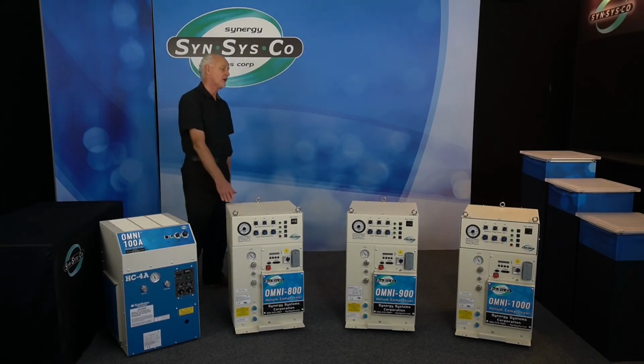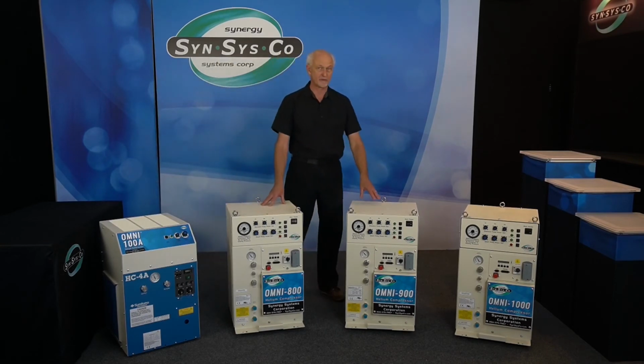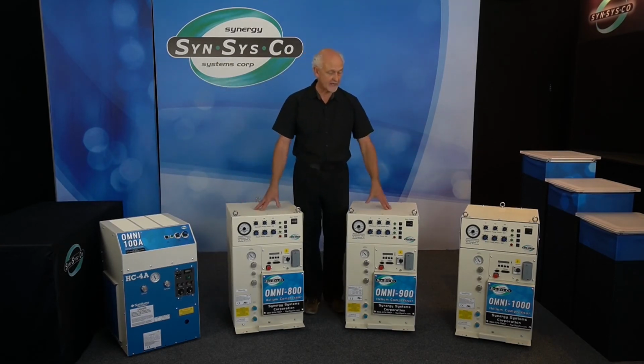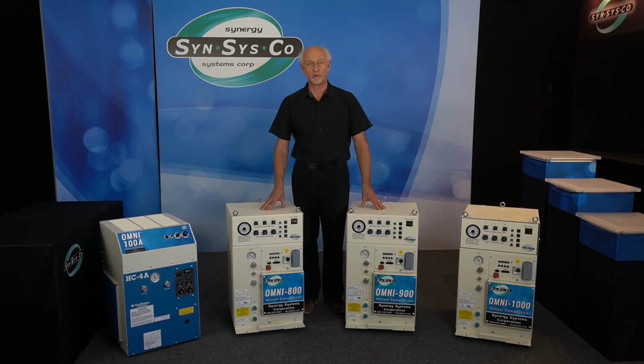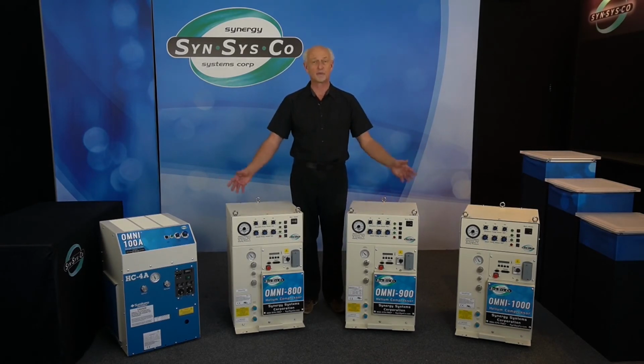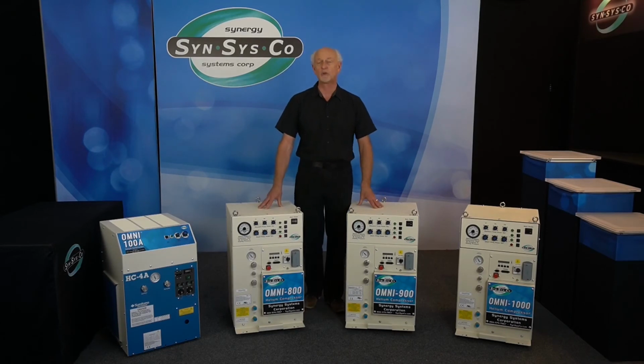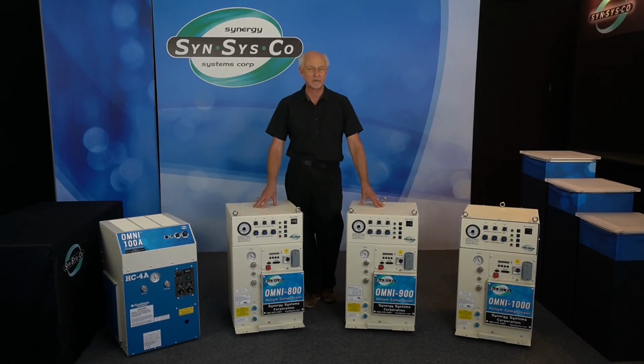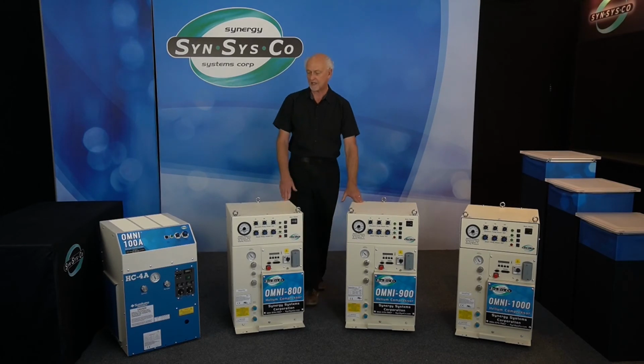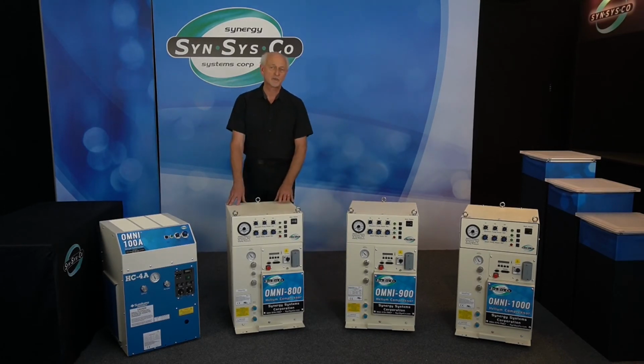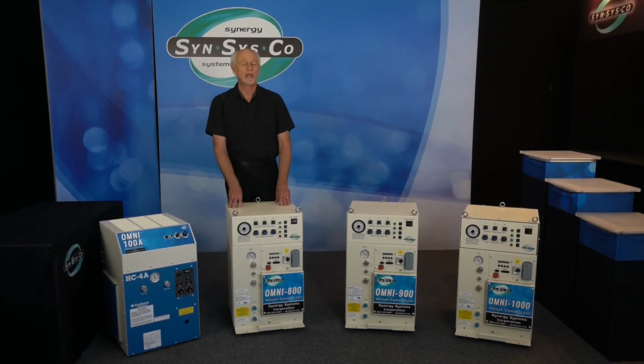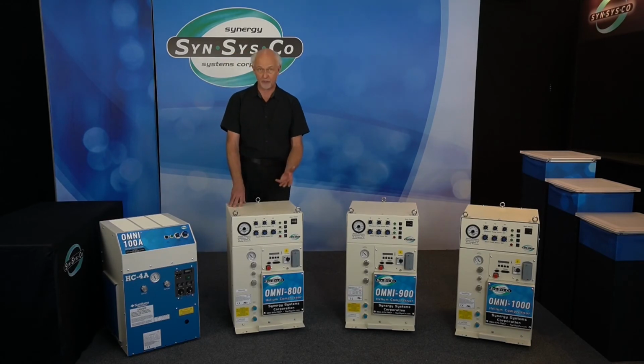Now let's take a look at the other three compressors in the family. You'll notice right off that in fit and form they're identical. They have the same footprint, they have the same height, they have the same connections. They vary only in the ampacity needed to drive them and in the displacement of the internal helium capsule and in the charge pressures used to run your pumps. Let's take the OMNI 800. This compressor can drive two 8-inch pumps or one 10-inch pump.